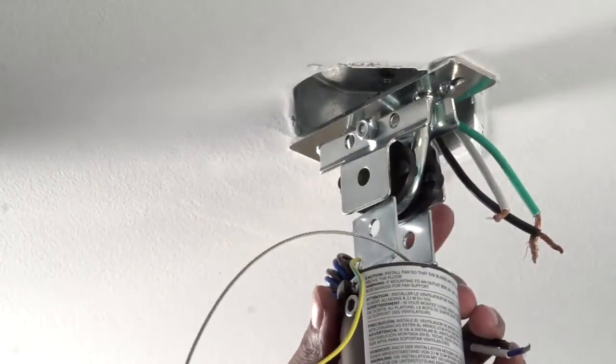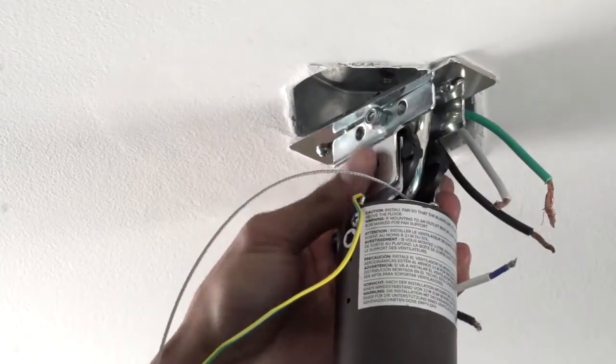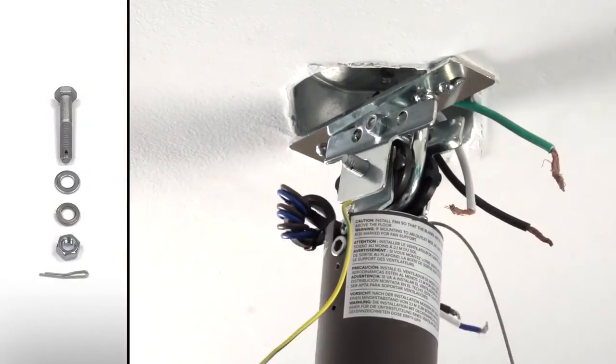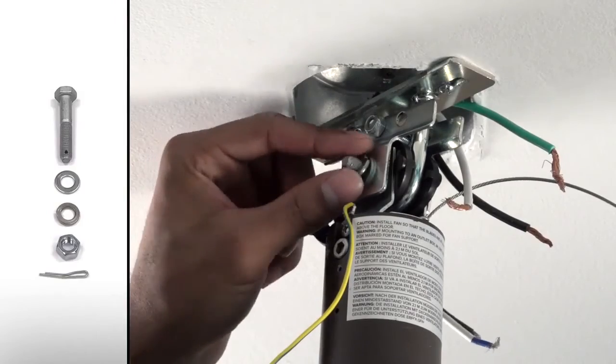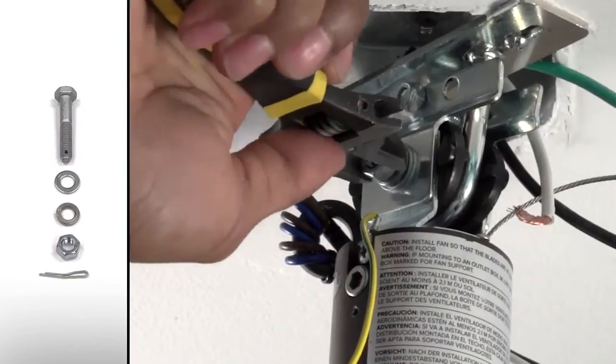Raise the extension tube to the outlet box, ensuring extension tube brackets are inserted between mounting brace brackets and rubber bushing so that mounting holes are aligned. Insert the bolt through the holes and secure on the other side with flat washer, lock washer, and nut. Tighten all hardware.